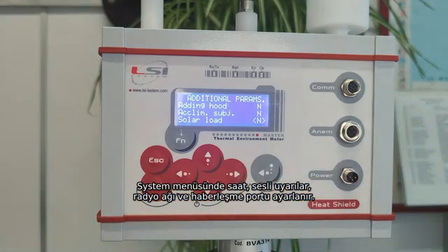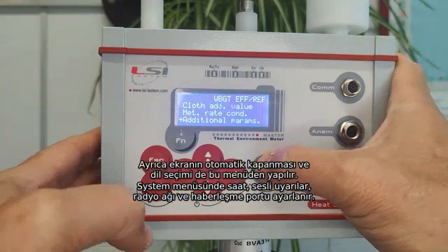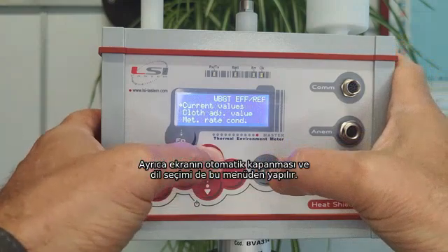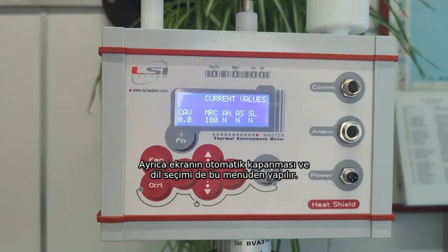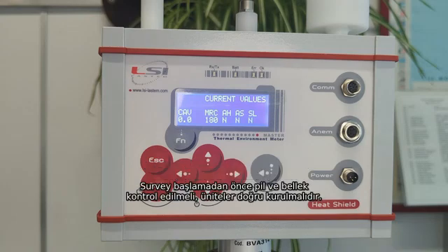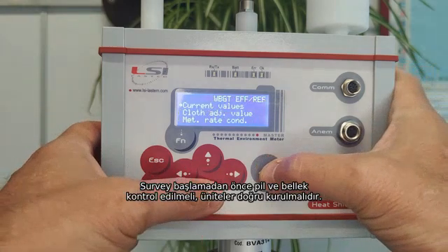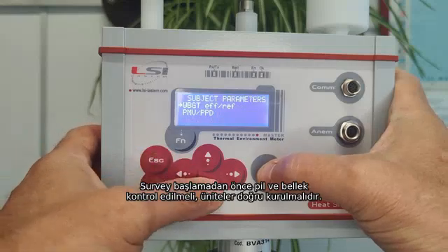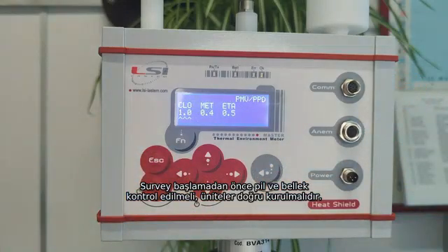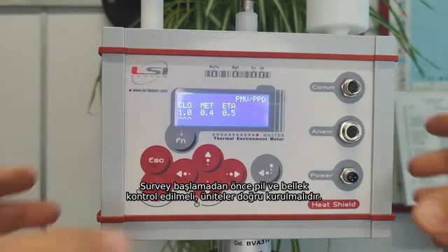Type of subject, acclimatized or not acclimatized, and the type of WBGT formula to be used, with or without solar load. All these additional parameters are summarized in the current values selection: clothing adjustment value, metabolic rate condition, hood presence, acclimatized subject and solar load formula selections. For the PMV-PPD calculation, clothing, metabolism, and mechanical work values should be set properly.